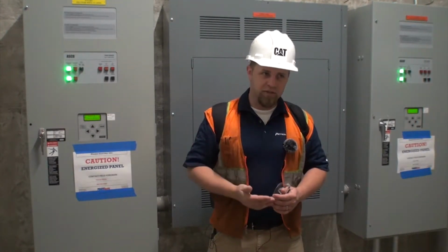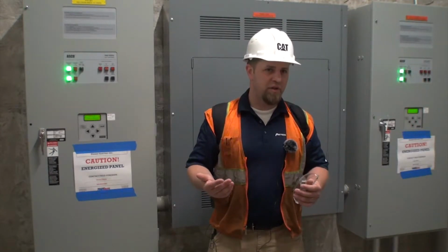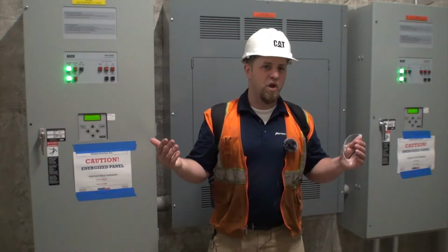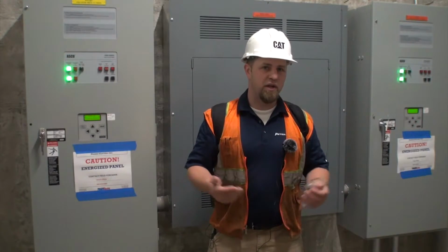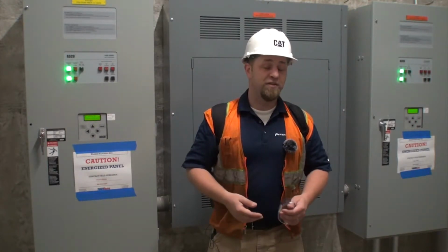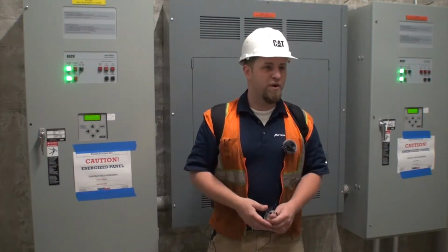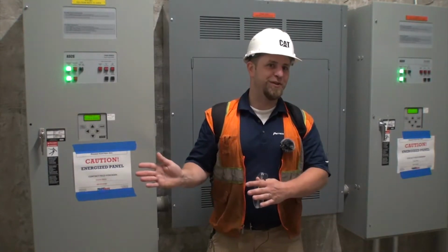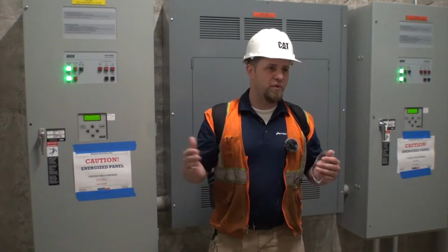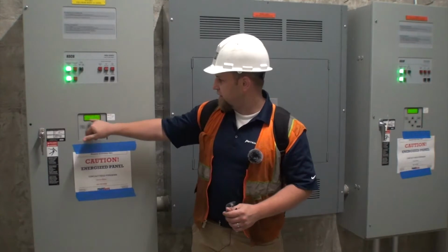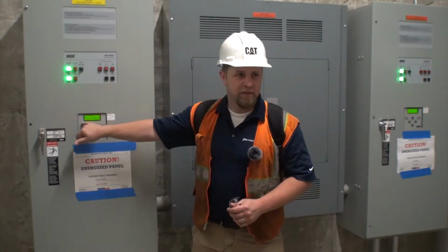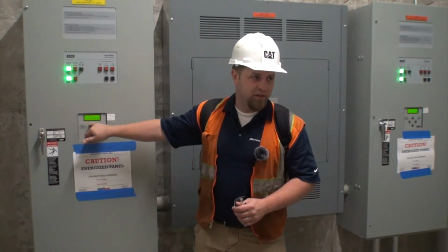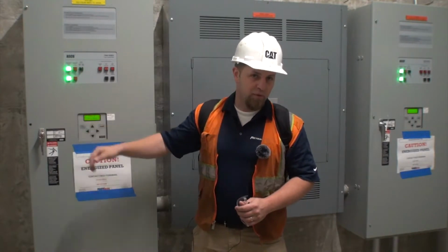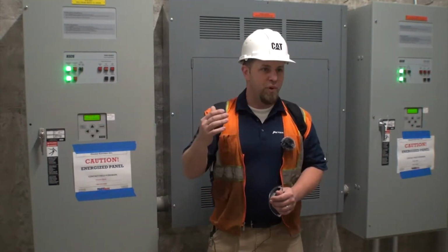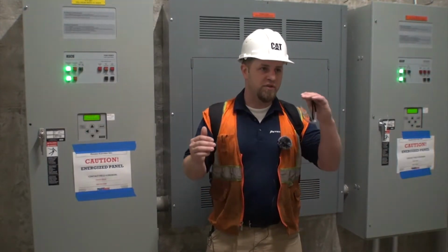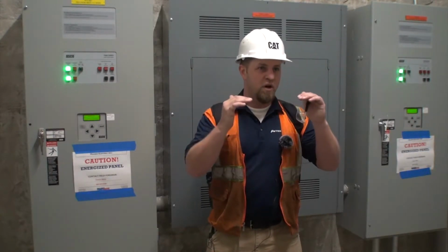So I get lots of phone calls like, 'hey, we had a power outage, the rest of the building's back up and going, but the generator's still running.' I've had people call me 2 days later saying the generator's been running for 2 days. That's extreme, but if it's running for 2 or 3 hours, you'll see little lines on here showing it's still trying to sync. It'll have a timer sitting there trying to reboot, but it also wants the hertz and volts to be close before it transfers.